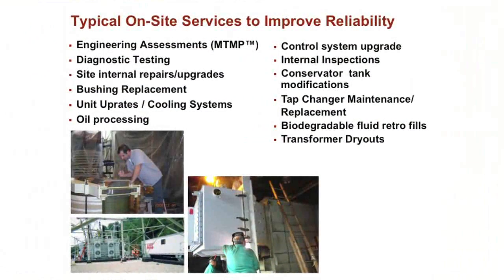If you have bushings where certain vintages are known to have a high risk of failure, or if you see the power factor creeping up. Doing upgrades in the cooling system. This is where you take out the old cooling system and put in something larger or more effective. Processing the oil, to improve the dielectric properties of the oil. I'm going to go through all of these individually. And then doing a cooling or control system upgrade. Internal inspection can be very good. This is where you take the unit out of service, drain the oil, and a design engineer goes inside and looks for what issues can be seen.